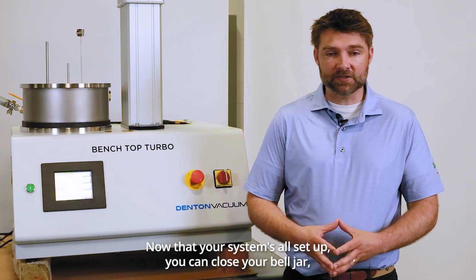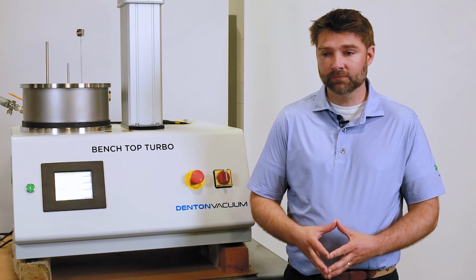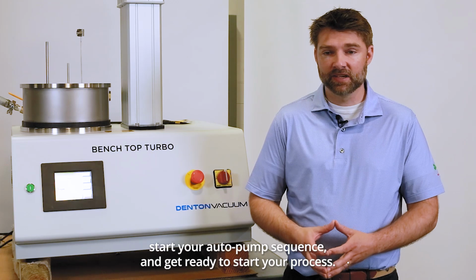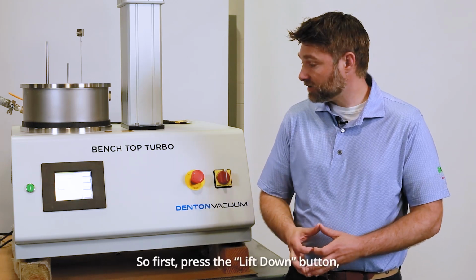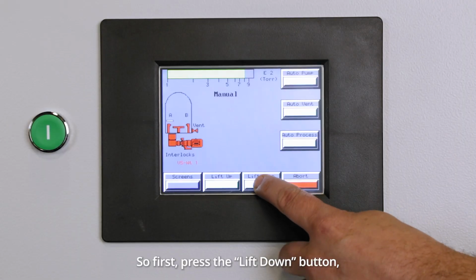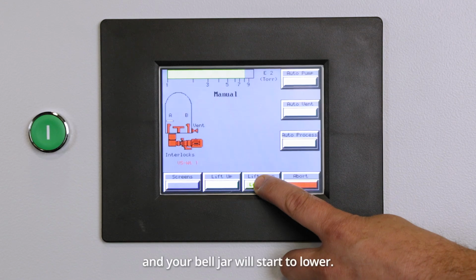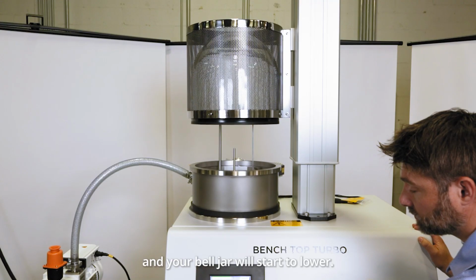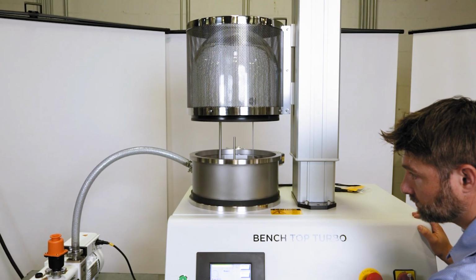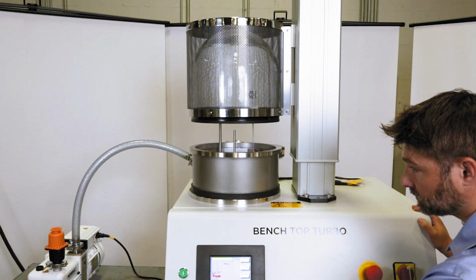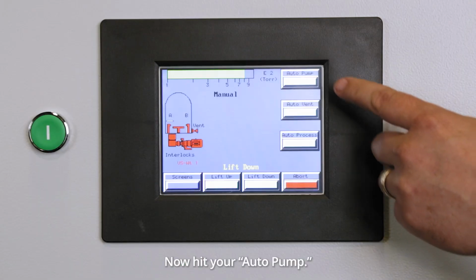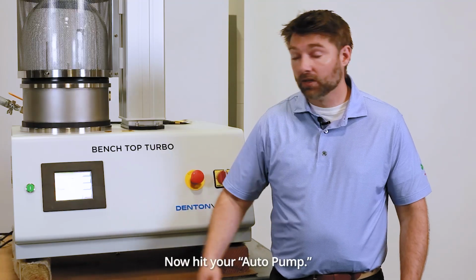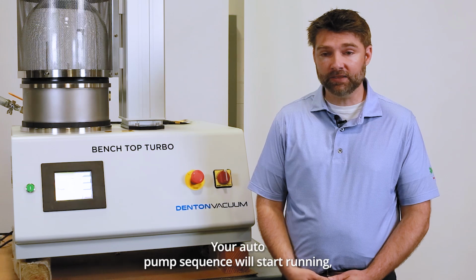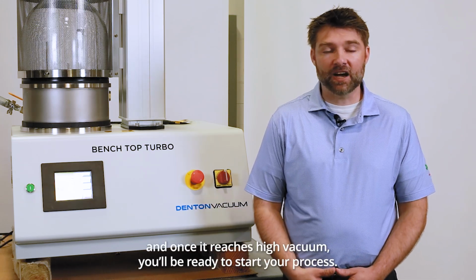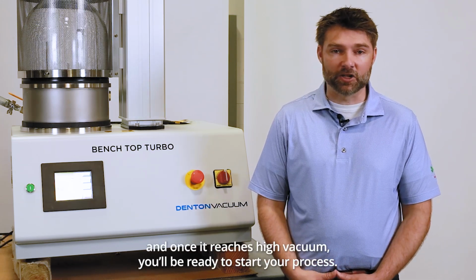Now that your system's all set up, you can close your bell jar, start your auto pump sequence, and get ready to start your process. So first, press the lift down button, and your bell jar will start to lower. Now, hit your auto pump. Your auto pump sequence will start running. And once it reaches high vacuum, you'll be ready to start your process.